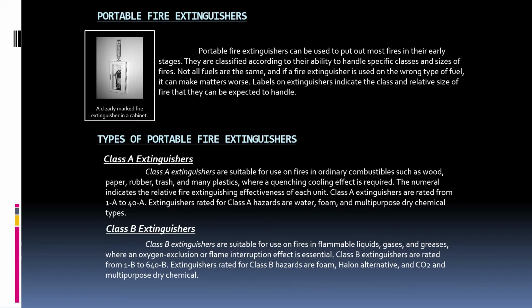There are four types of portable fire extinguishers. The first one is Class A extinguishers. Class A extinguishers are suitable for use on fires in ordinary combustibles such as wood, paper, rubber, trash, and many plastics, where a quenching cooling effect is required. The numeral indicates the relative fire extinguishing effectiveness of each unit. Class A extinguishers are rated from 1A to 40A. Extinguishers rated for Class A hazards are water, foam, and multipurpose dry chemical types.